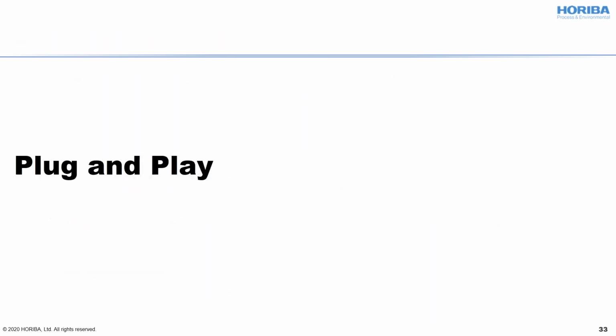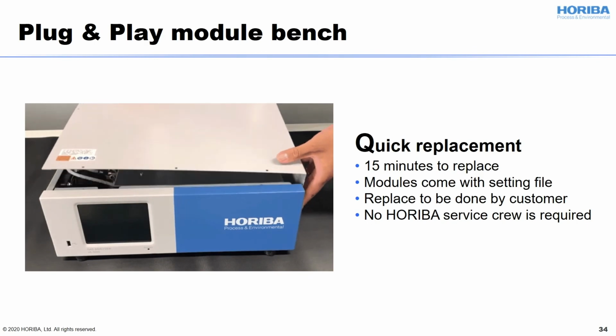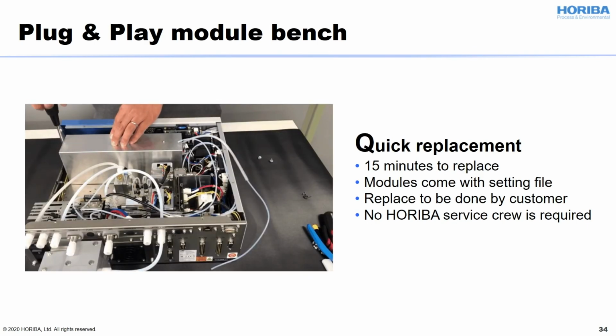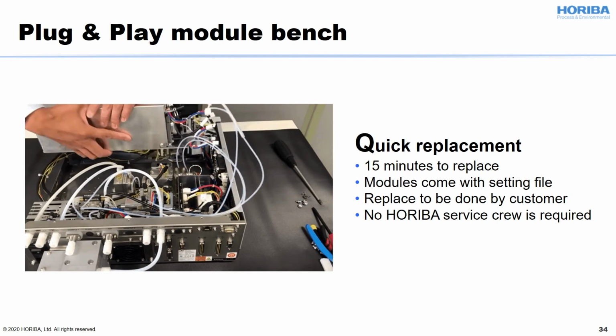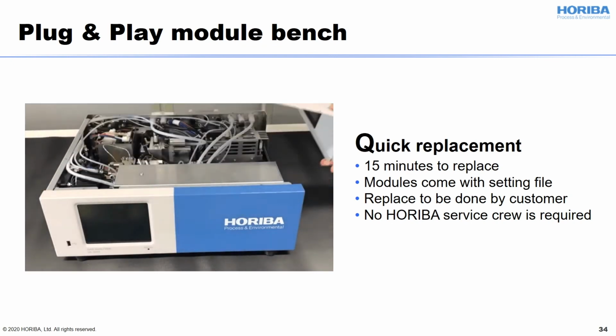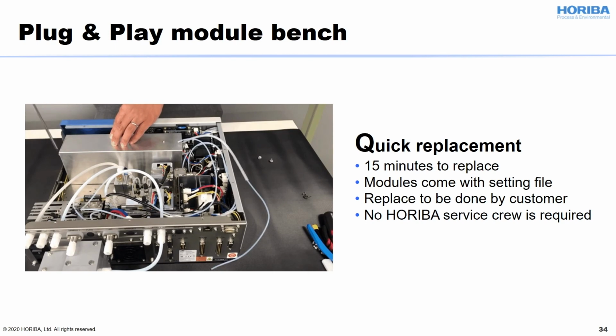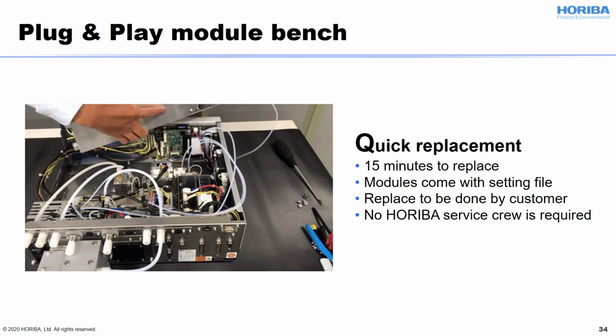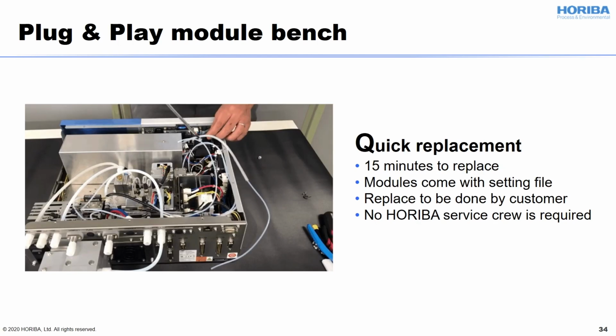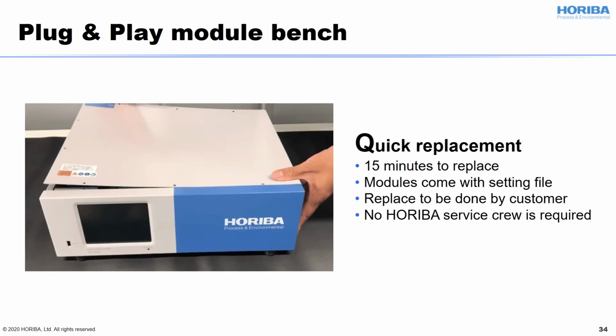The toughest thing for continuous measurement is always downtime, and sometimes you cannot wait for a service analyzer tech for the repair. HORIBA VA-5000 was designed for users. Users can replace the analyzer module themselves and reboot without a service tech. The silver box is the module you want to replace. It takes 15 minutes to replace, and you can load the file after replacement, then all set. No HORIBA service crew is required.